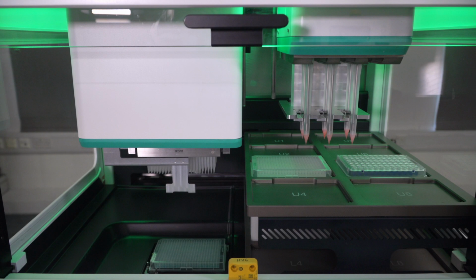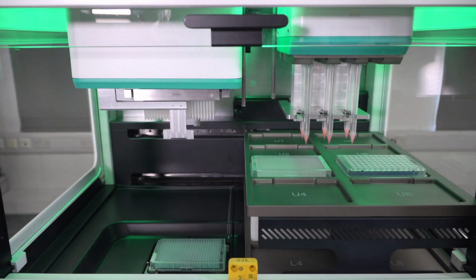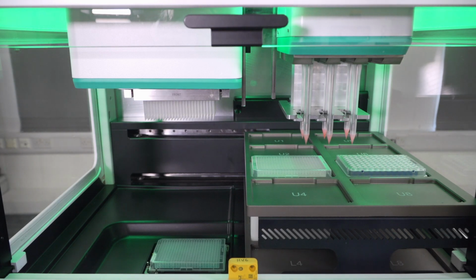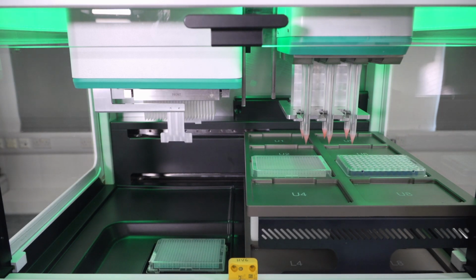So as the plate is loaded in, there's a little tab that will lock the plate into position securely and then shake. And I think this one is quite high speed, around about 2000 RPM. So it's quite effective even with 384 well plates. And we've found that, certainly in 96 well plates, we can resuspend bead pellets and so on quite effectively with the shaker. So it means you can effectively mix without having to waste tips using a tip mixing approach. Of course, if you want to do tip mixing, you can as well, so you've got total flexibility.